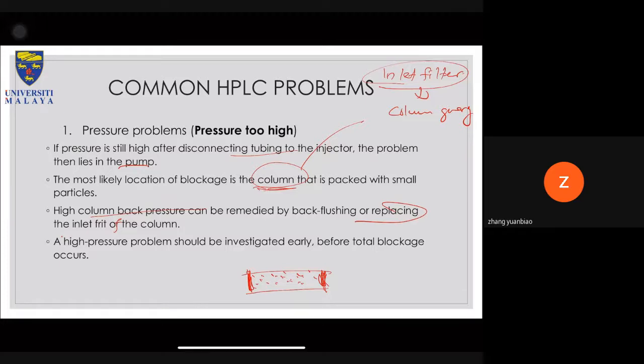All right, a high pressure problem should be investigated early, before total blockage occurs. So if originally it's 2,500 psi, and then on the day of your run it suddenly jumps to 4,000 psi, even though the system still runs perfectly, you might want to stop what you are doing and investigate before it goes to 5,000 and blocks your system from running altogether. All right.